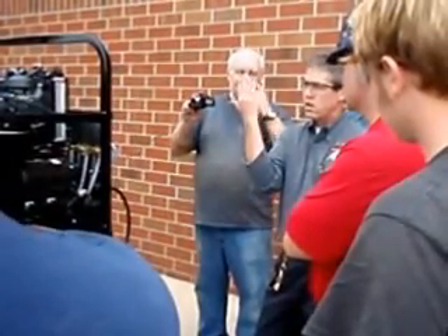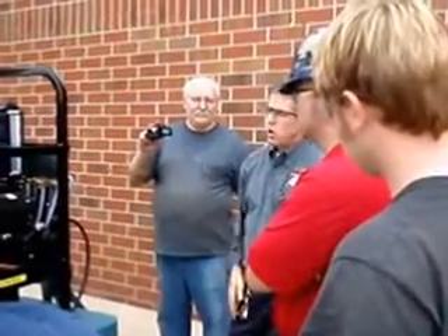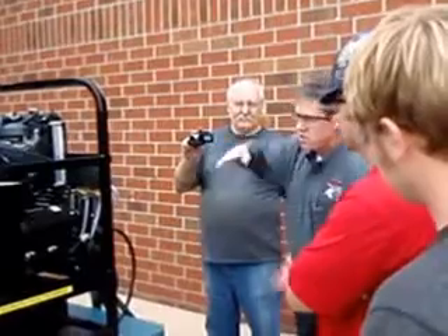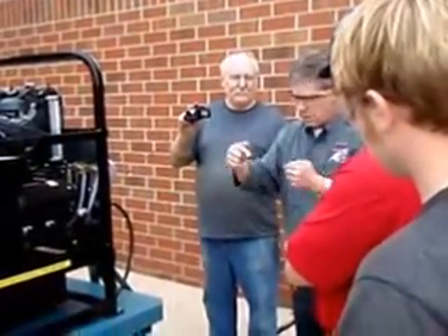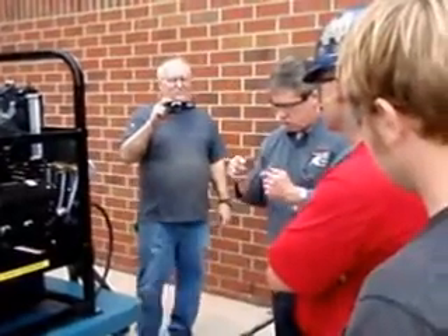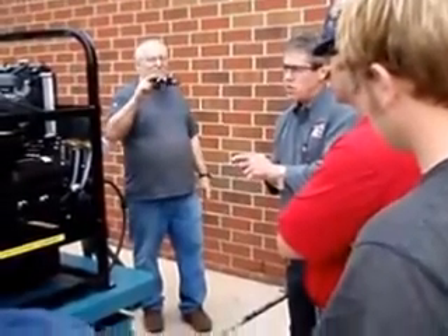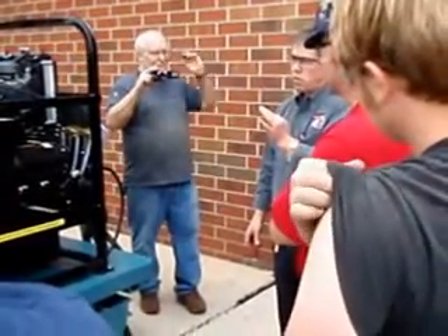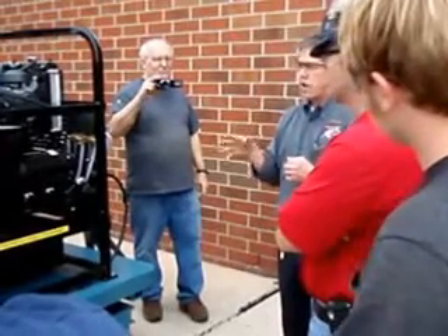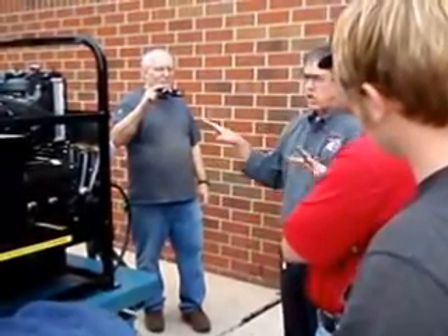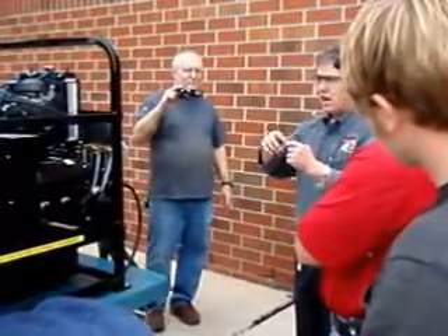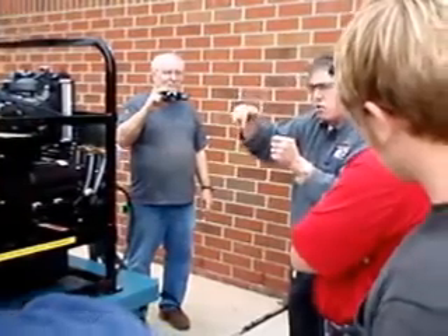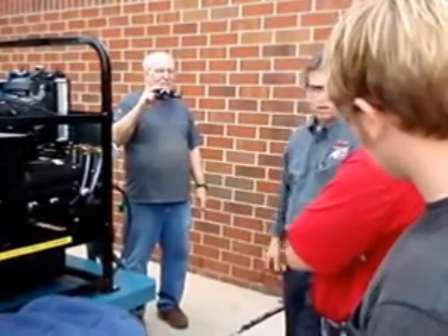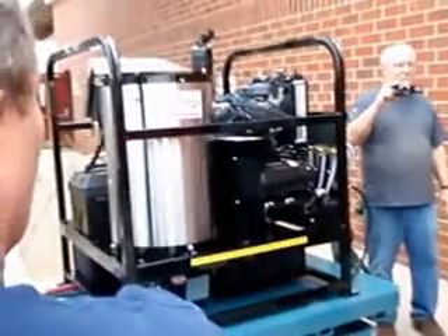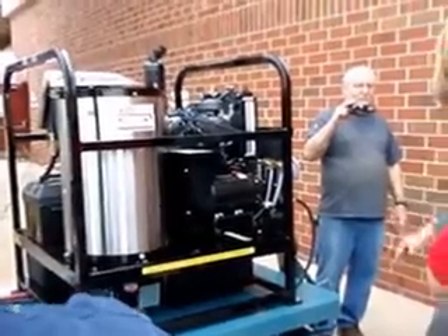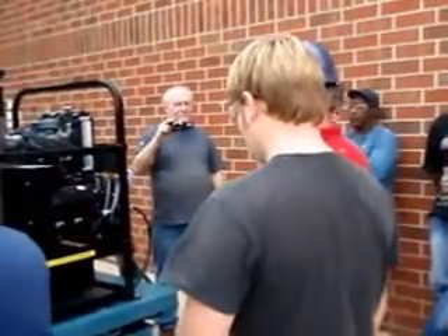Your burner nozzle sitting in there like this is supposed to be like this. So if that machine is tilted up just a smidge, your burner gun, and like I said, we've got some cutaways, it's about that long. There's a tube about that long to the nozzle, and it's a quarter inch. It's full of fuel. So when you're triggering up, just like what you're saying, the fuel solenoid is what shuts that fuel down, so you've got a delay. You're exactly right. Anything that's in that line is going to drip. There's nothing to stop it. With this, your design element with standing up is a whole lot less potential. Not to mean it won't happen, but there's a whole lot less potential.